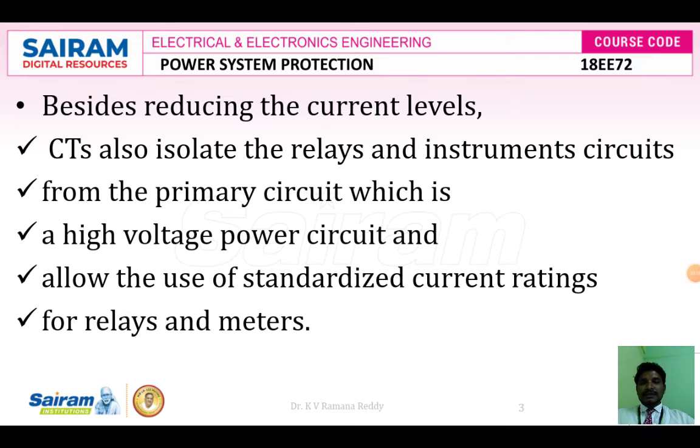Besides reducing the current levels, current transformers also isolate the relay and instrument circuits from the primary circuit, which is a high voltage power circuit, and also enable the use of standardized current ratings for relays and meters. That's why nowadays many companies manufacture current transformers, but there should be certain standards while we are using the current transformer to step down the primary current level to the secondary current level.